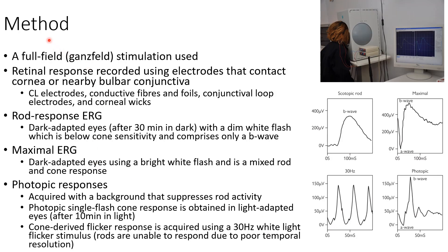Now let us discuss the method of full-field ERG. A full-field, that is Ganzfeld, stimulation is used, as you can see in this picture. The retinal response is recorded using electrodes that contact the cornea or nearby bulbar conjunctiva. We can use contact lens electrodes, conductive fibers and foils, conjunctival loop electrodes, and corneal wicks.